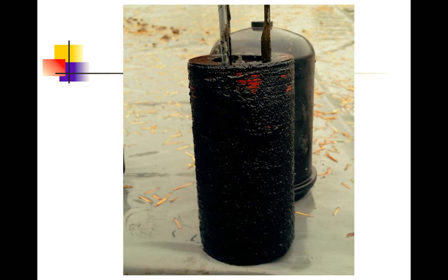A normal functioning system will have a disc filter that looks like this. This looks really bad. It looks like it's clogged and no liquid would go through it. This filter was actually taken out of one of the systems that we tested at NSF, and this has been running for close to 8 months, and it still has the exact same flow and pressure characteristics as it did the day it was started with a brand new clean disc filter.